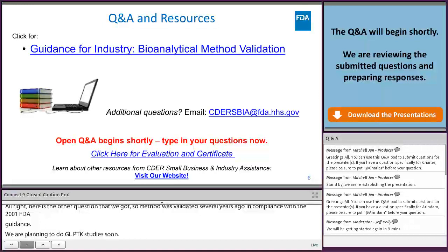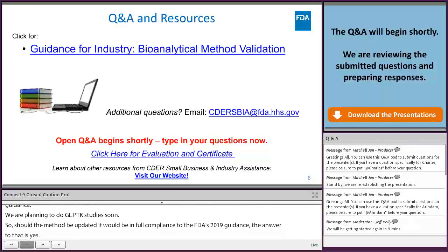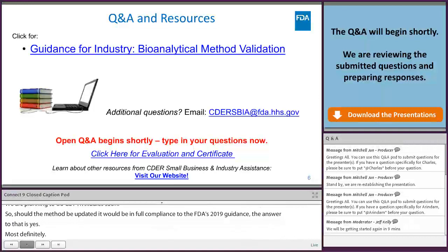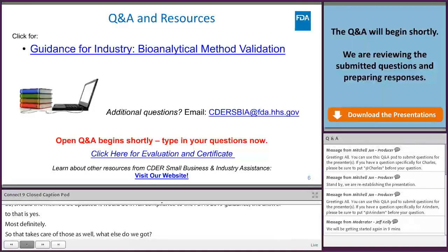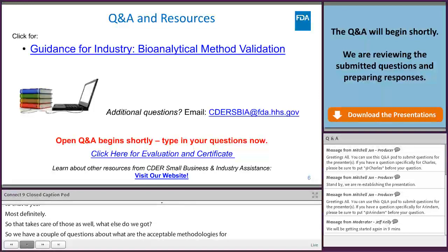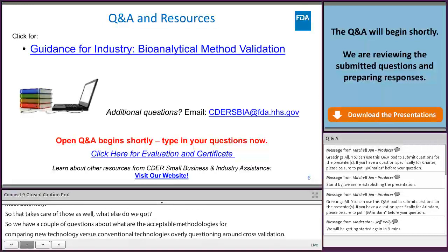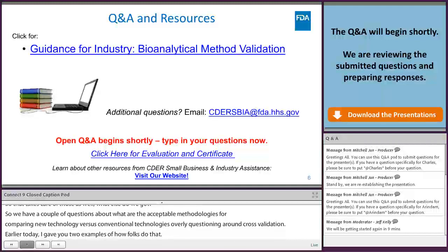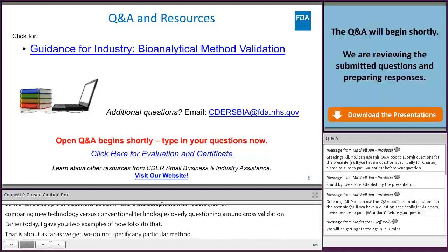What else have we got over here? So we had a couple of questions about what are acceptable methodologies for comparing new technology versus conventional technology. So really a question around cross-validation. Earlier today I gave you two examples of how folks do that, and that's about as far as we get in the guidance. We don't specify any particular method. One thing to consider though is most people are doing the case where they're running the samples on both methods and regressing the answers against each other. So you get a linear regression.